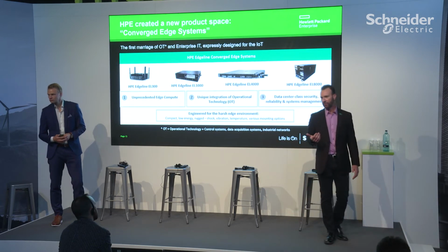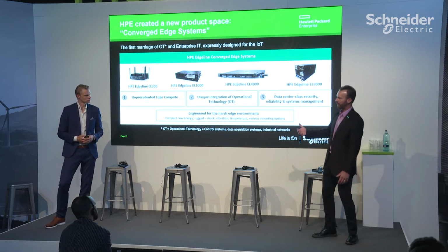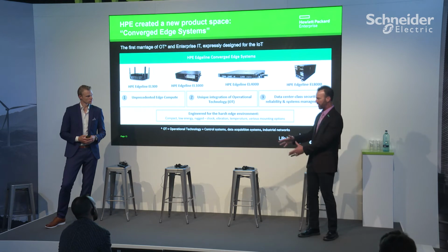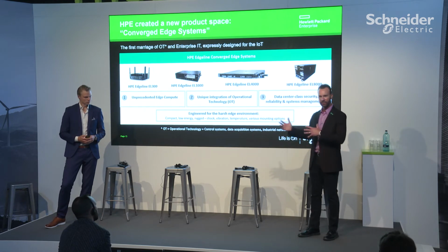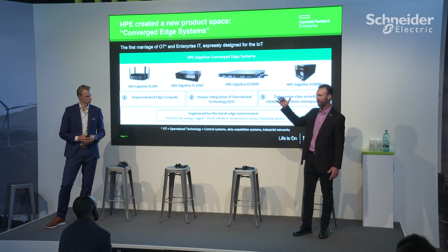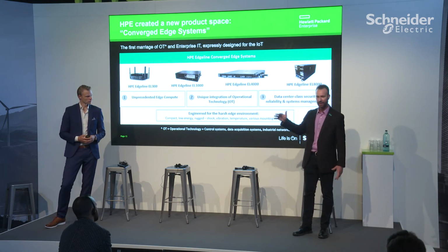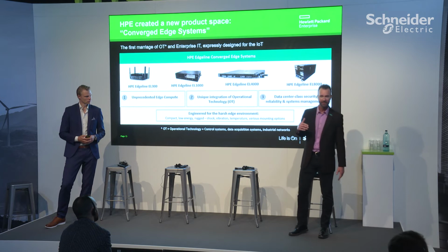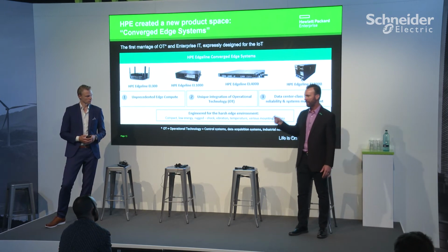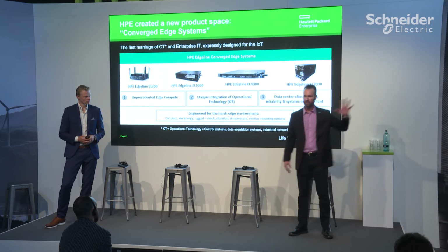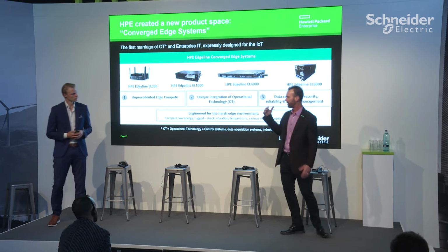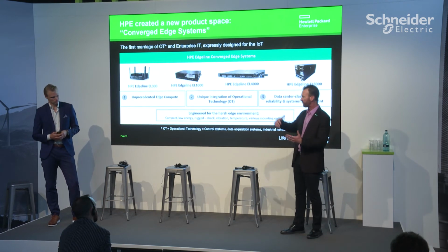Now what we're able to automate is this: when I get a power outage and see that I'm draining through the UPS for a certain amount of time, I'm getting to a time-critical piece. Not only can I make sure I get graceful shutdown of my workloads if that's what I want to do, the other thing we can now do is initiate an immediate backup of those VMs onto an adjacent system, with all of that automated based on the integration of our systems and your systems together.